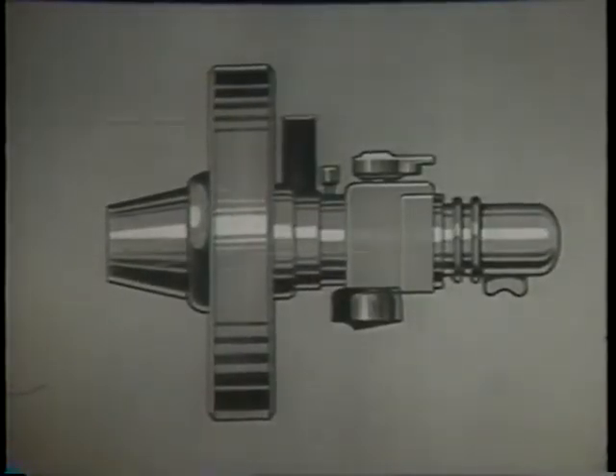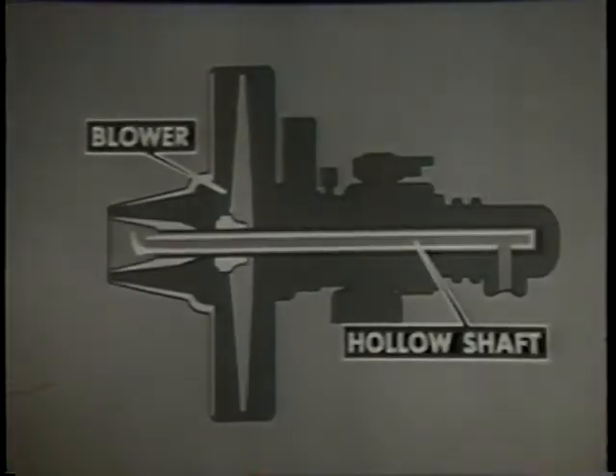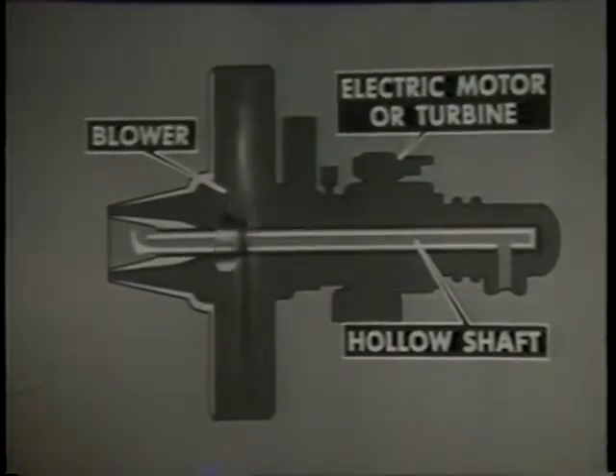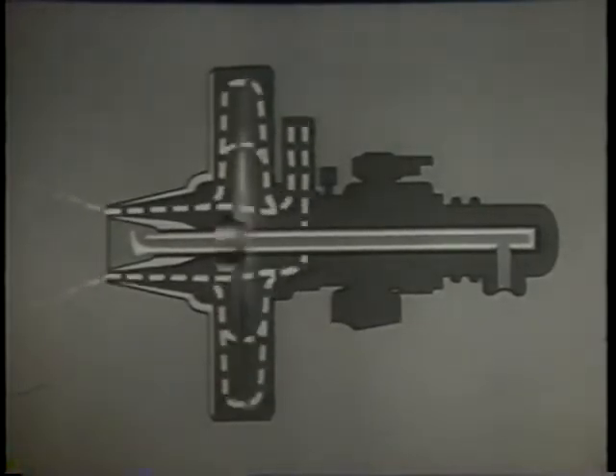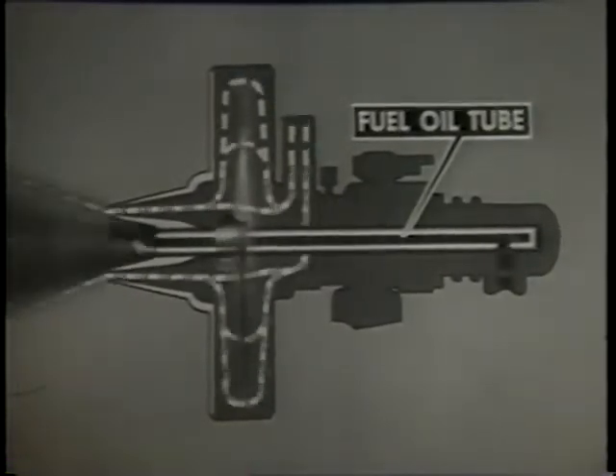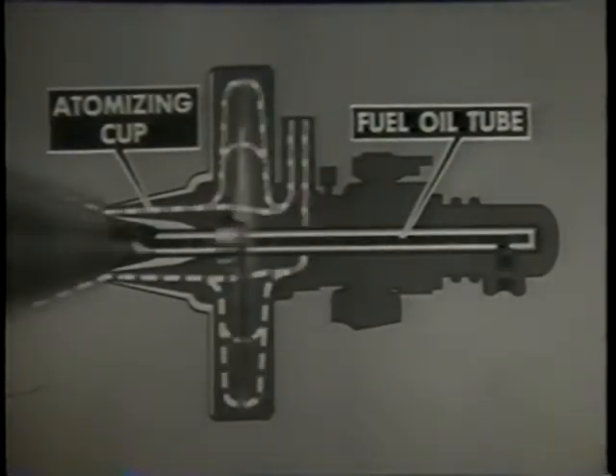In the rotary cup burner, a fan or blower is mounted on a hollow steel shaft. An electric motor or steam turbine turns the shaft and blower at high speed, providing a blast of air around the burner nozzle. The oil, under low pressure, enters through a stationary fuel oil tube inside the rotating hollow shaft and is discharged into the rotating atomizing cup. Centrifugal action forces the oil against the inner surface of the atomizing cup and causes the oil to leave the rim as a hollow cone. The meeting of the oil and the air from the blower further atomizes the oil.